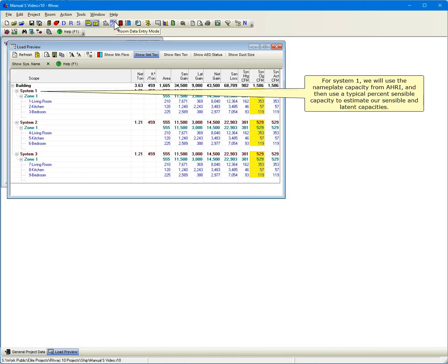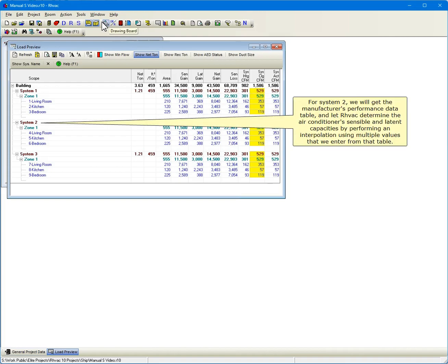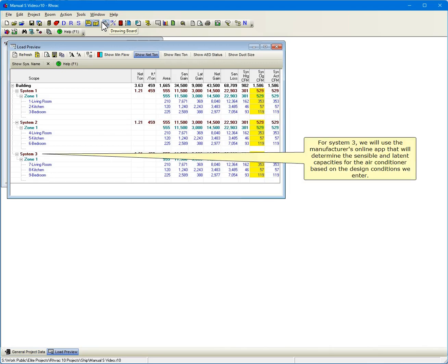For System 1, we will use the nameplate capacity from AHRI and then use a typical percent sensible capacity to estimate our sensible and latent capacities. For System 2, we will get the manufacturer's performance data table and let RHVAC determine the air conditioner's sensible and latent capacities by performing an interpolation using multiple values that we enter from that table. For System 3, we will use the manufacturer's online app that will determine the sensible and latent capacities for the air conditioner based on the design conditions we enter.